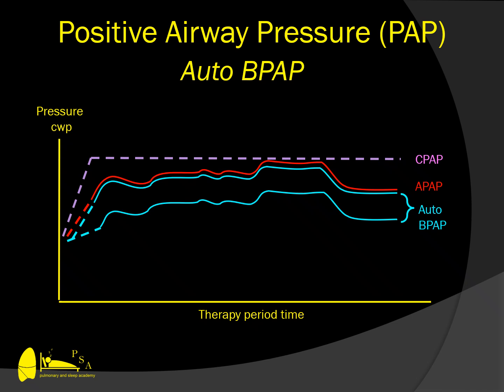This actually is a comfort feature that is at some cost. And so to go to a bilevel positive airway pressure machine, we're generally talking about something that's twice as costly. And so whether it's the patient's cost or the insurance cost, one option is to just utilize the expiratory features that are already on the original PAP machine. And in the Philips Respironics, it's a C-Flex feature, and in the ResMed, it's called EPR, or expiratory pressure reduction. And so you can actually set those features at, say, a setting of 2 or 3 to reduce pressure with exhalation, and this may be enough to not have to go to a formal auto bilevel device.